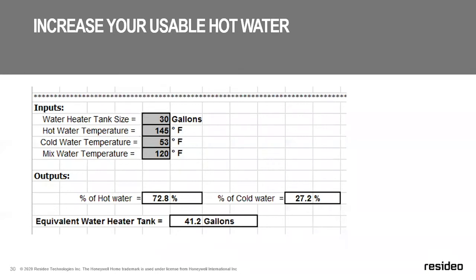We could put in a 30-gallon. Let's say we set the tank to 145 degrees. Our incoming water from the city or street is 53, and we're going to set the output of the mixing valve to 120. So what we'll actually get out of that 30-gallon is 41.2 gallons of hot water. And that's because we're injecting cold water, which is about 27%, mixed with our 73% of hot water, and we're increasing our capacity by 11.2 gallons.